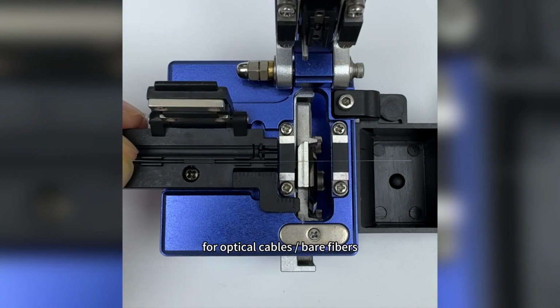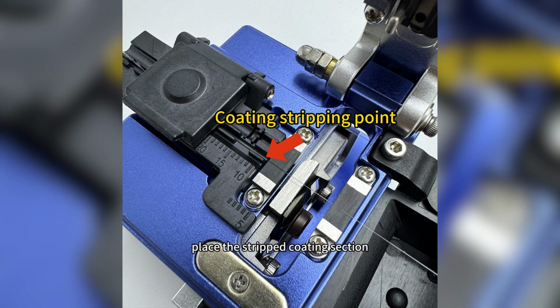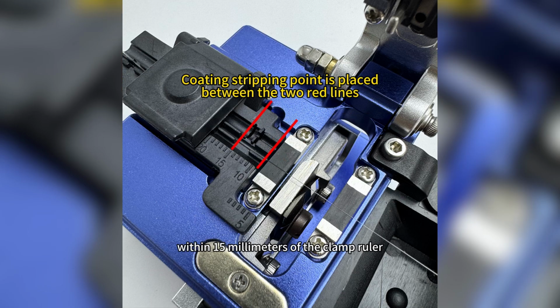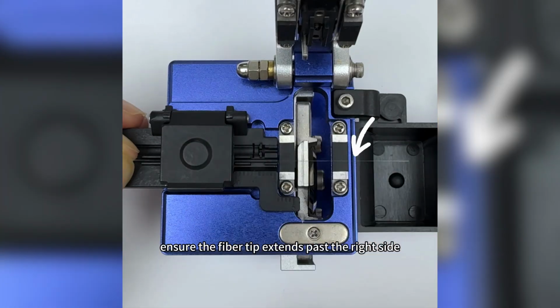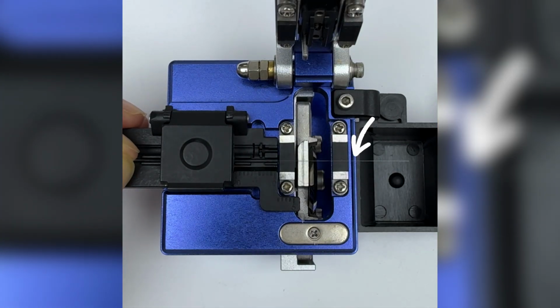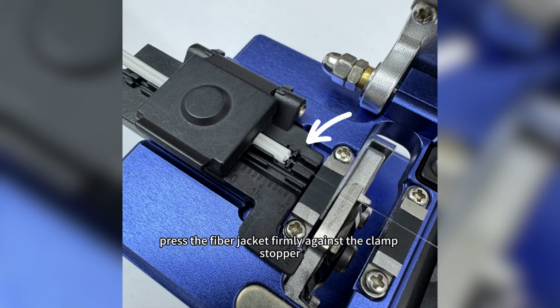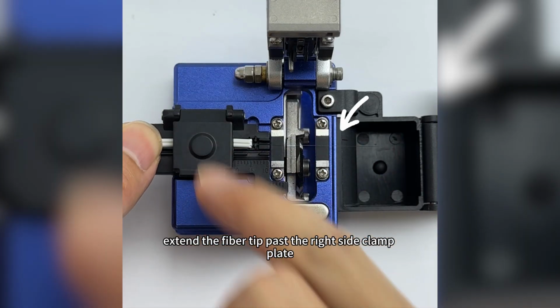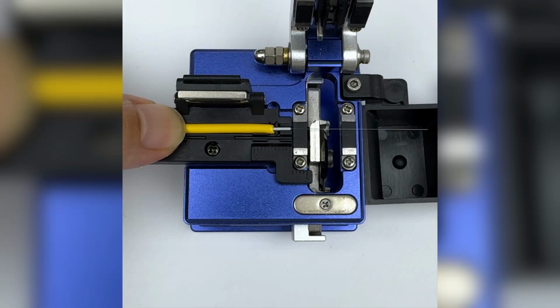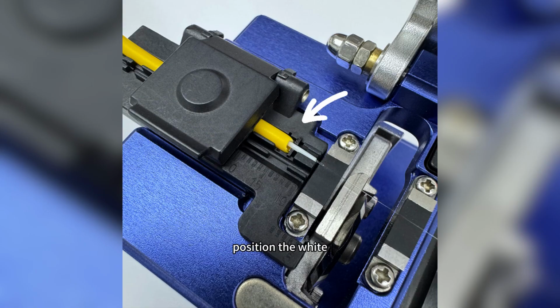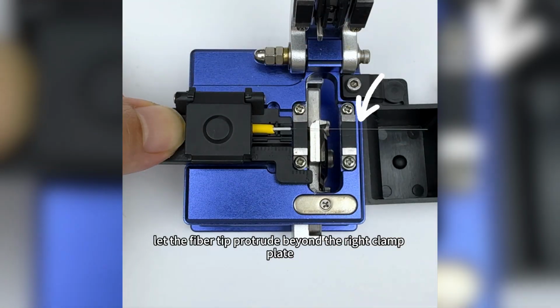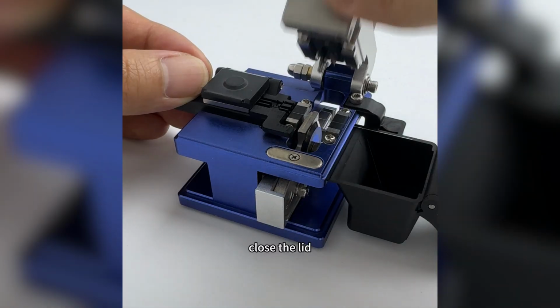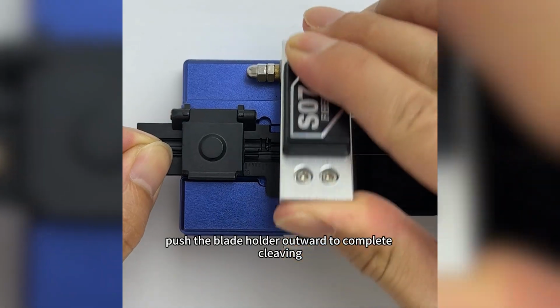Fiber cleaving. For optical cables or bare fibers, place the stripped coating section within 15 mm of the clamp ruler. Ensure the fiber tip extends past the right side fiber clamp plate. For drop cable fibers, press the fiber jacket firmly against the clamp stopper. Extend the fiber tip past the right side clamp plate. For patch cords and pigtails, position the white inner core within 15 mm of the ruler. Let the fiber tip protrude beyond the right clamp plate. Close the lid. Push the blade holder outward to complete cleaving.